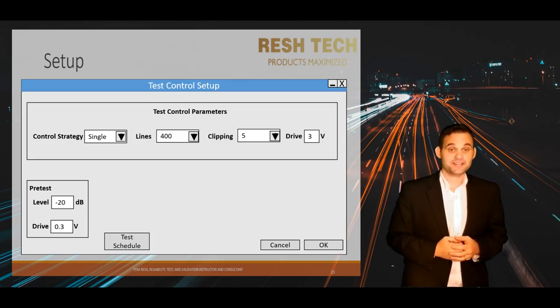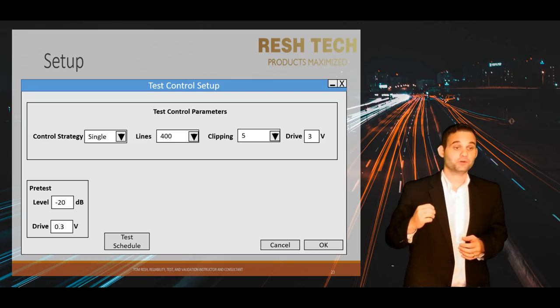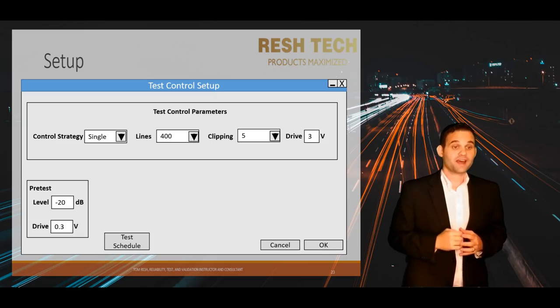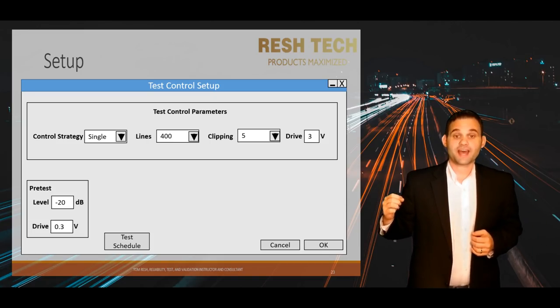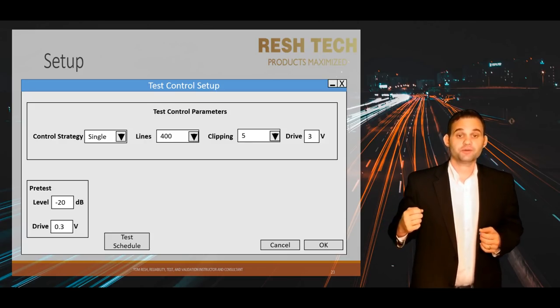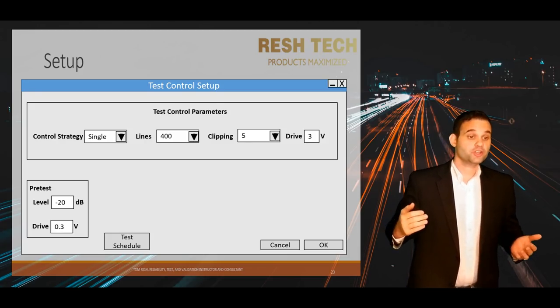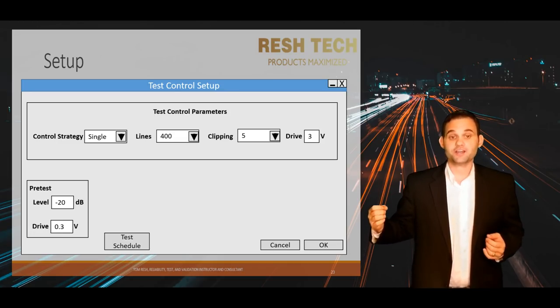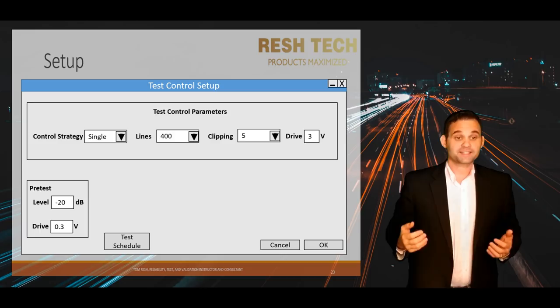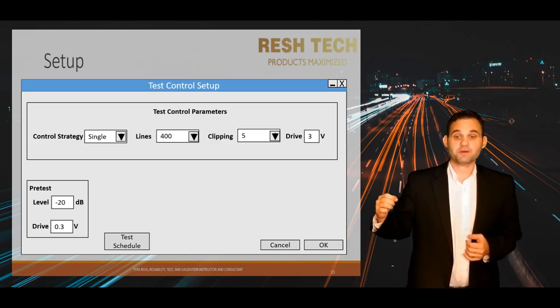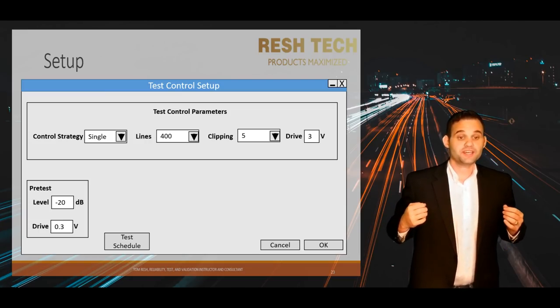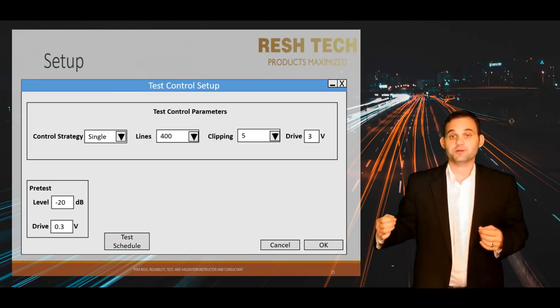Weighted average is an averaged weighted algorithm based on the feedback signal from each accelerometer to determine adjustments that need to be made to the drive output signal to maintain control to your test profile requirements. Max and min control strategies will use the maximum and minimum values for all of your control signals to produce the future drive output signal.